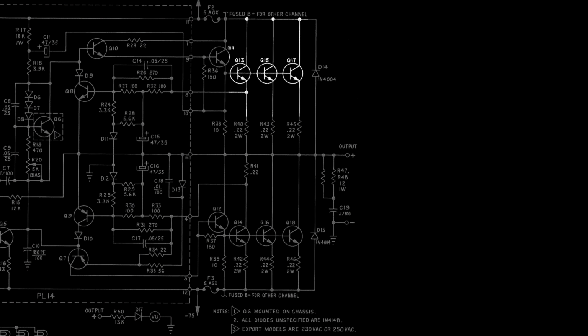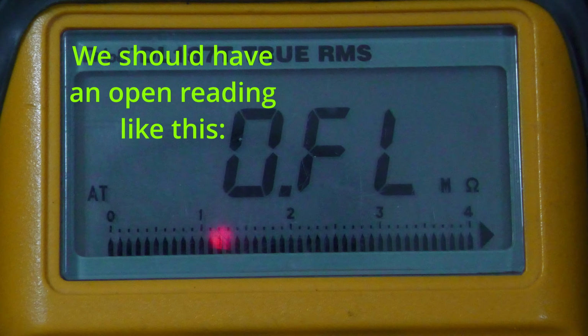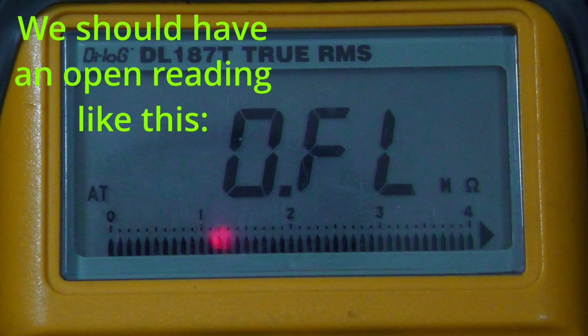All of the output transistors in each bank have their collectors tied together on a bus bar. Placing a positive probe on that collector bus bar, we see an open reading. All these collectors on this bank are isolated from chassis ground and are fine.